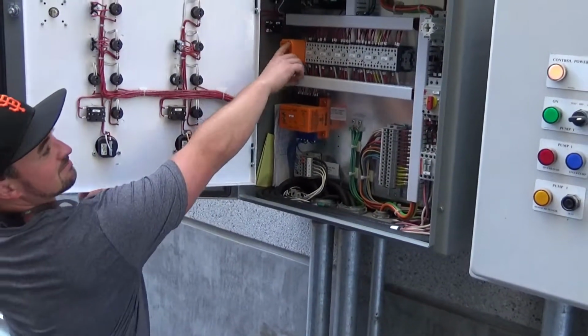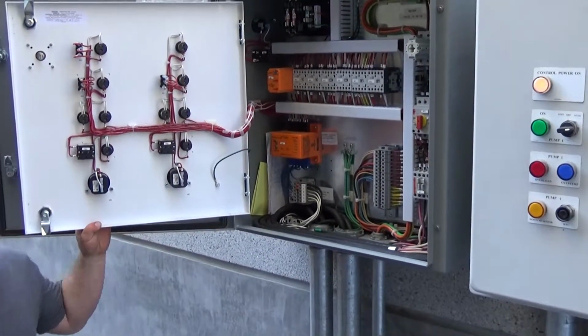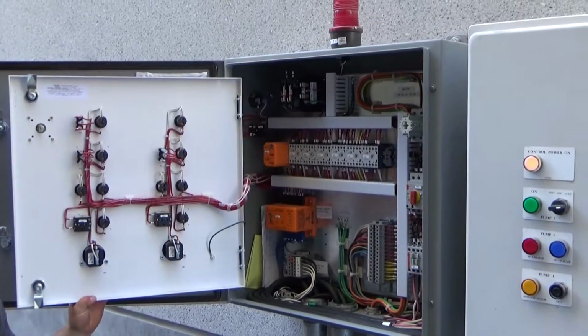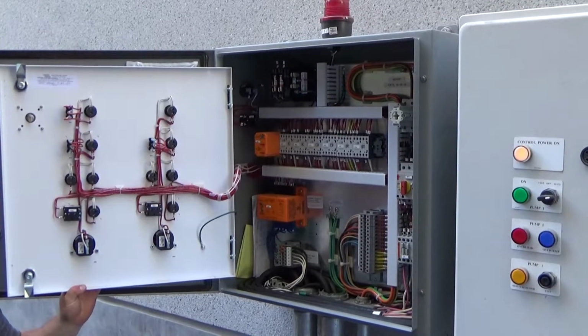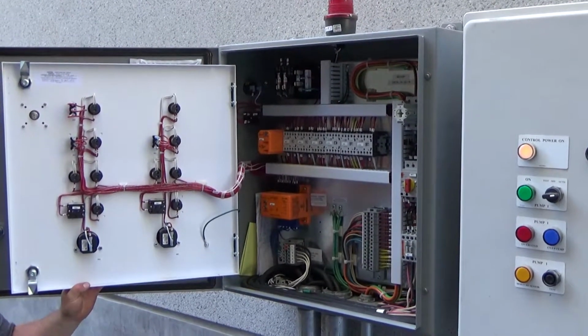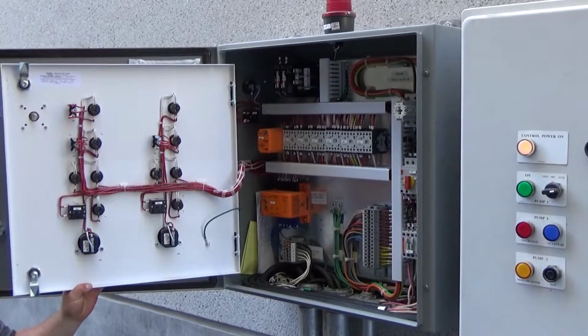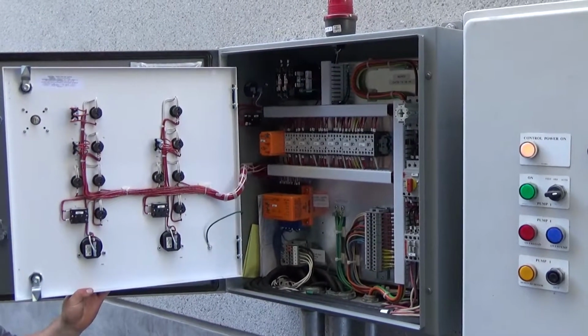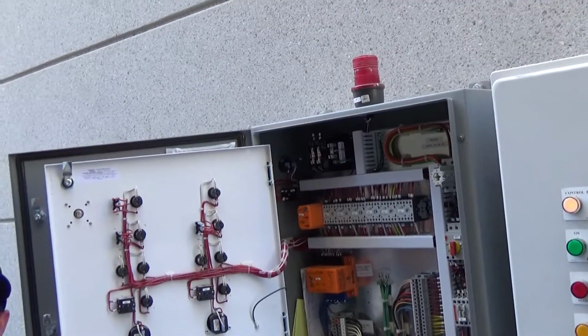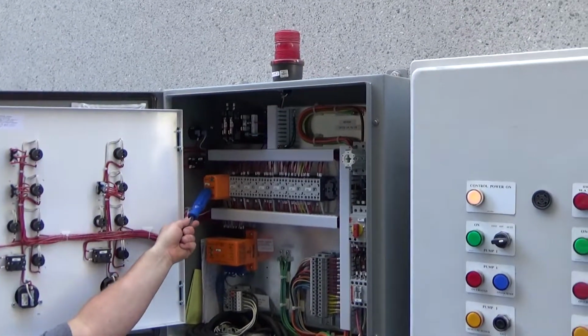Don't mess with that. That's the sensitivity of your moisture sensor. So that's your ohms. Turn it to 10. It's going to obviously trip. I think 100 ohms is what they have that sensor at. So can you point to that again and say, "Don't mess with that"? Don't touch that.